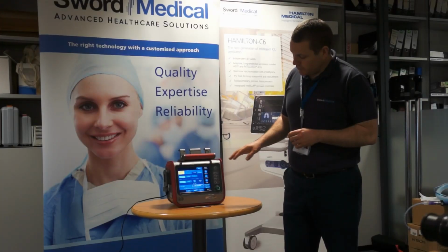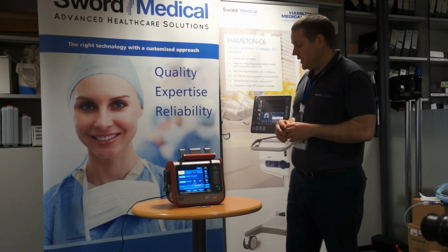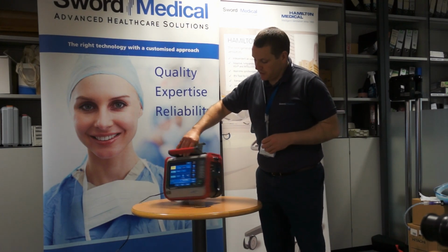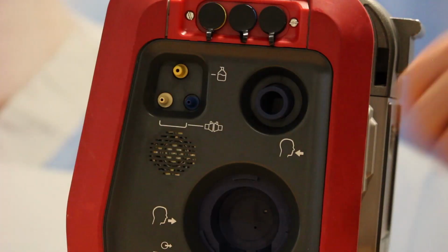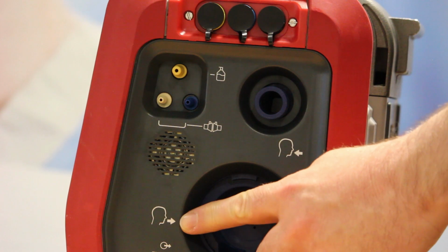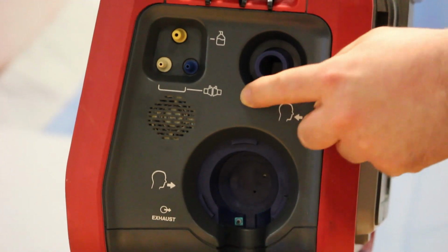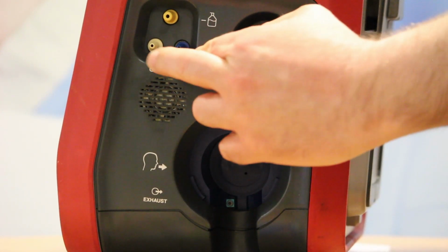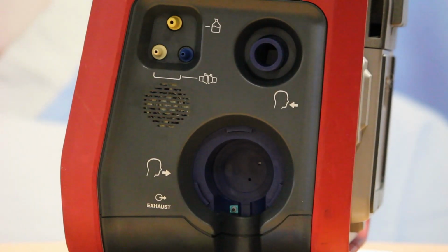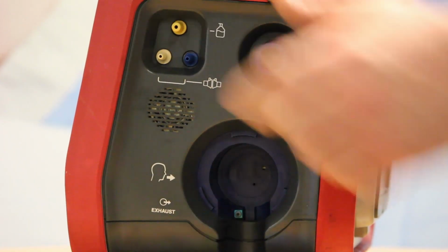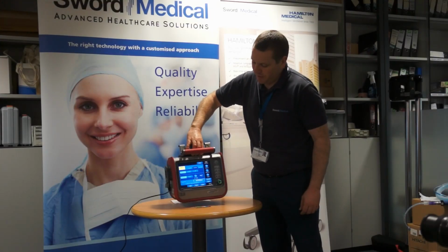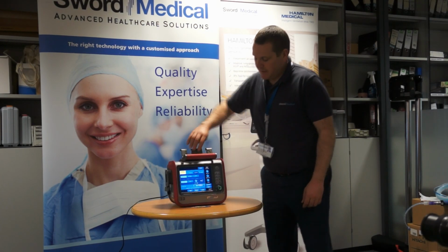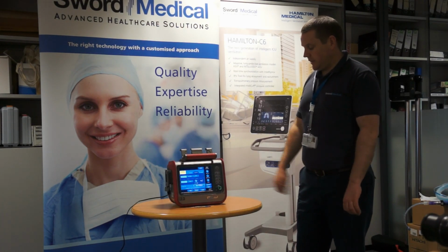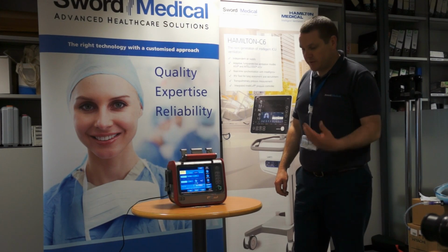So I'll just run through some of the buttons, and then we're going to put on a circuit. I'll just show you the part of the ventilator we're going to put the circuit on. So we've got our expiratory port here, picture a guide there pointing out. We've got our inspiratory port, picture a guide there pointing in. And then we've got our blue and our white ports where the flow sensor is going to plug in. And we've got a yellow port, and that is for an internal pneumatic nebulizer. You can plug the neb tubing onto that, and the vent will sequence the neb.